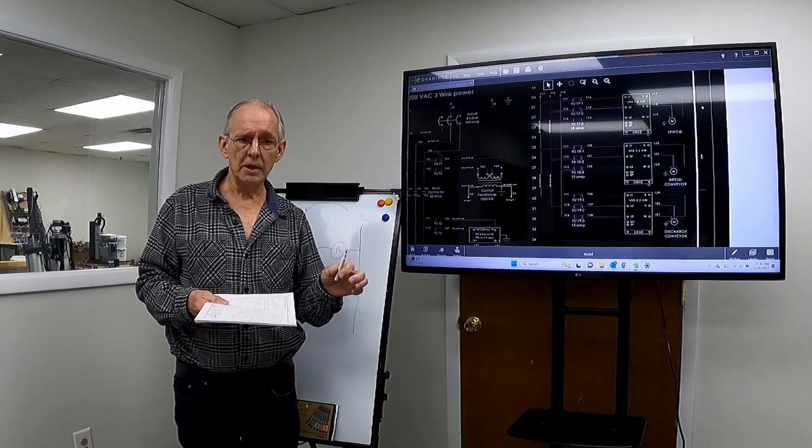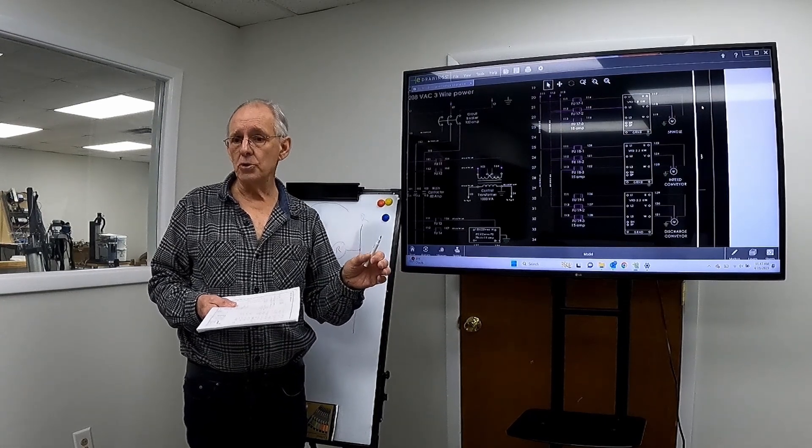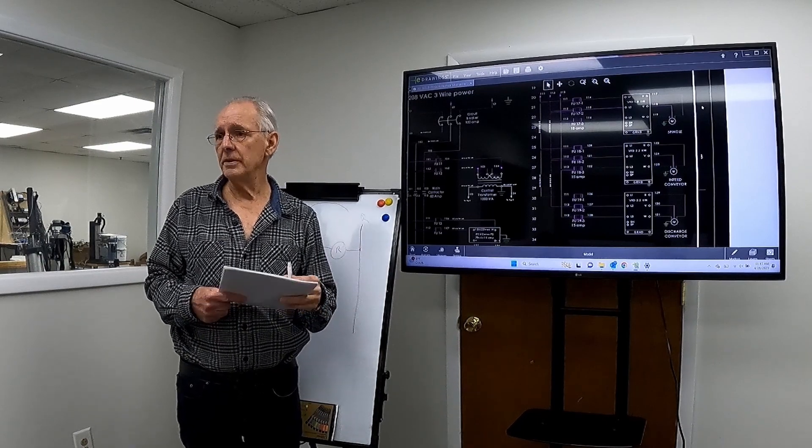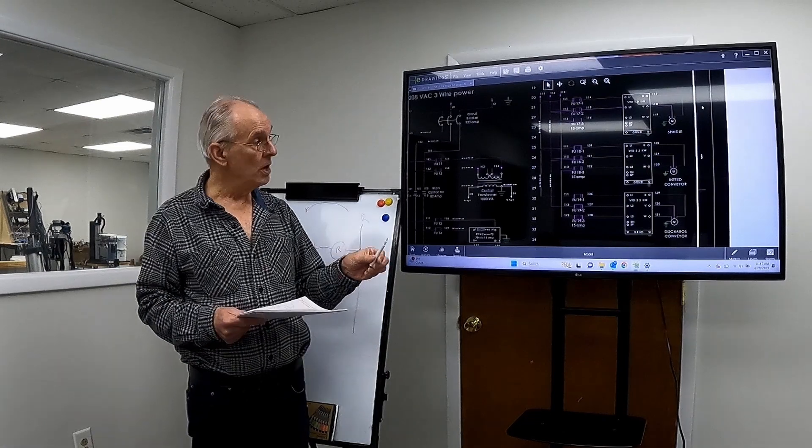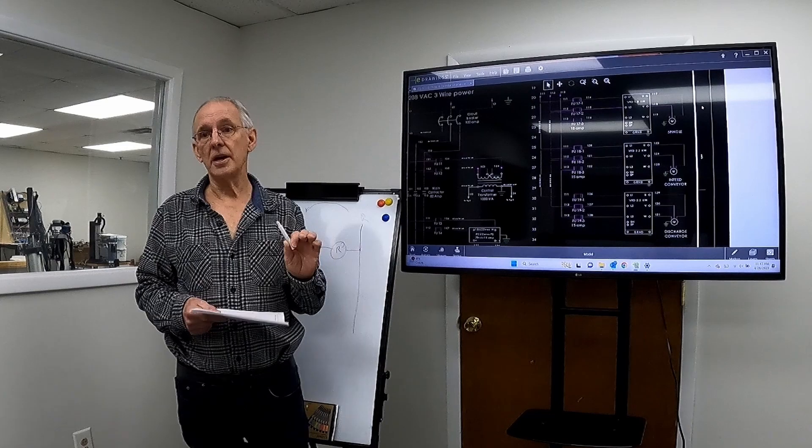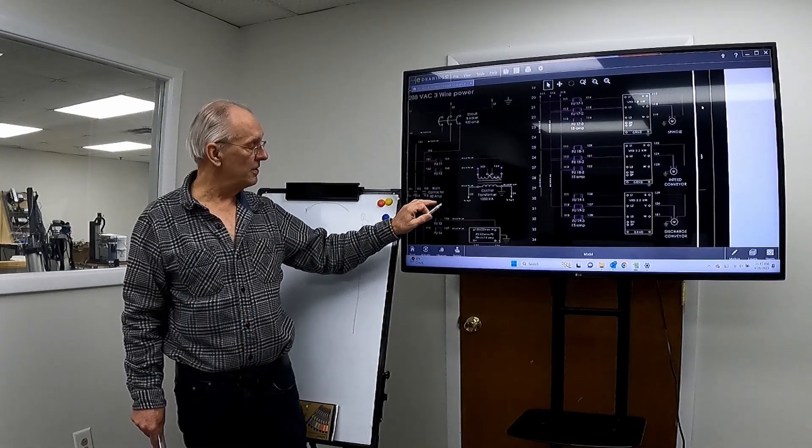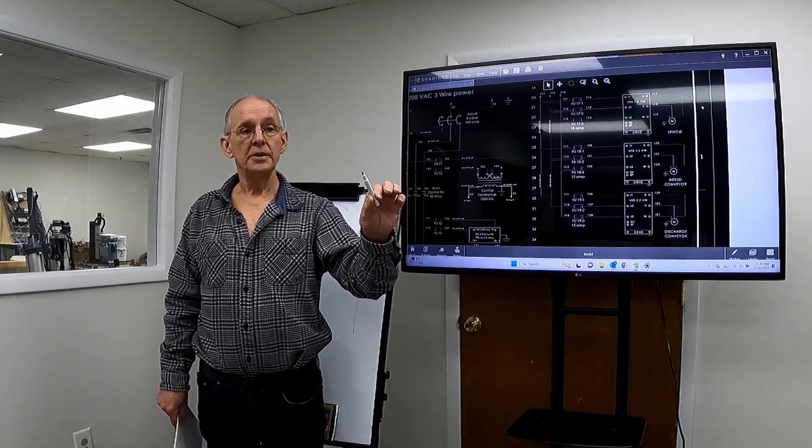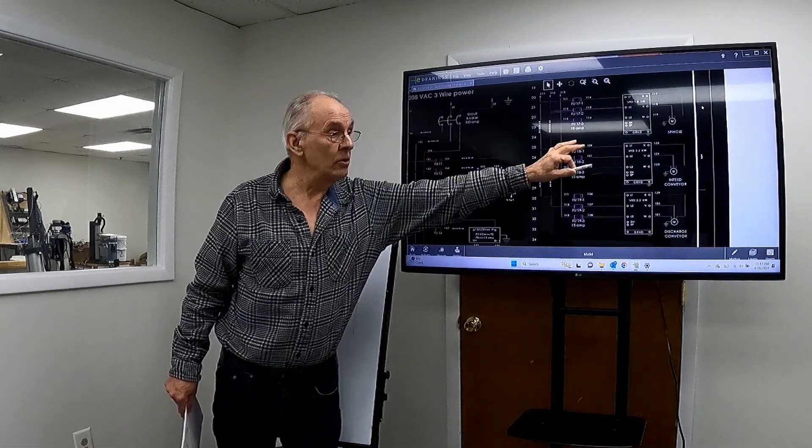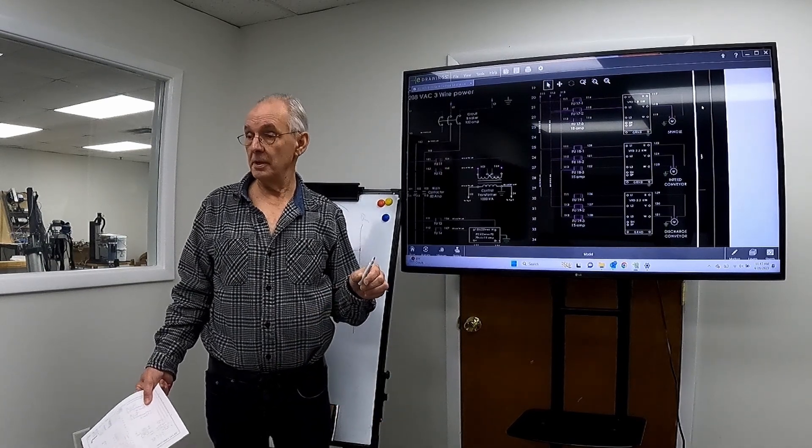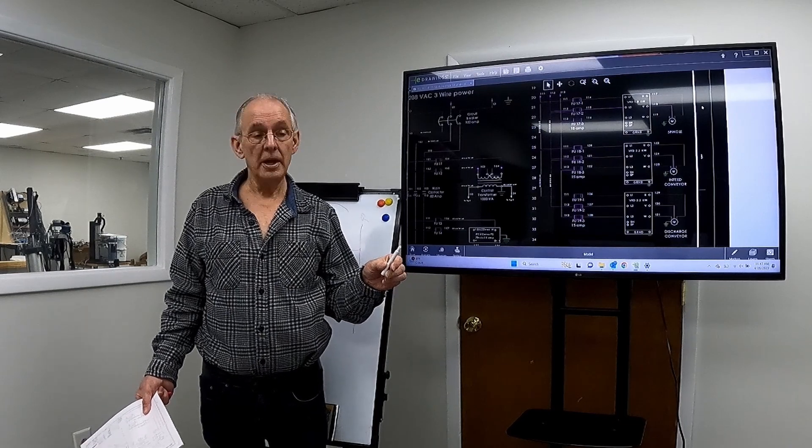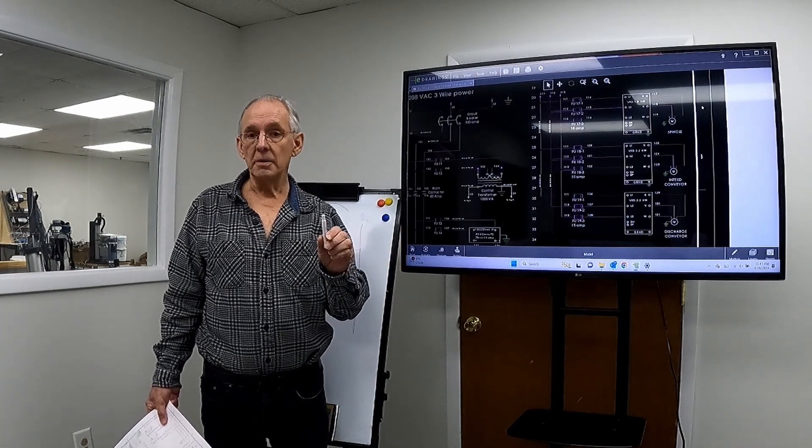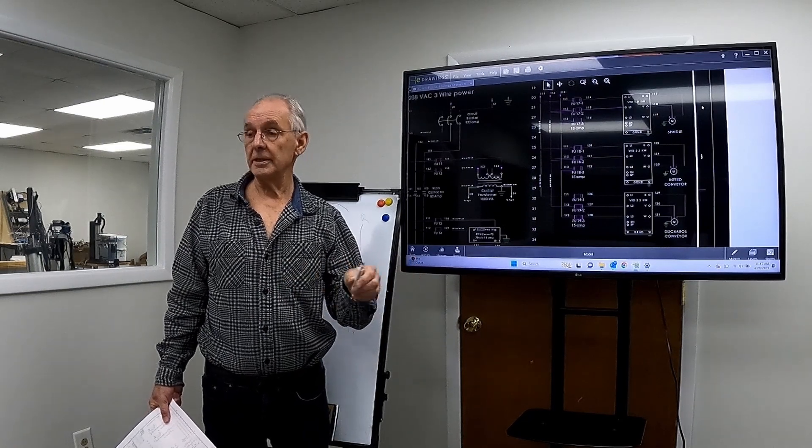So in doing safety, what we do is we try to break as much of the things that can turn on as possible. So we're shutting off the VFDs' power, but what if this contactor failed? Well, in order to keep that from being a problem, we also break the outputs from the PLC that tell them to run. So that's where the safety gets complicated because there's a lot of redundancy involved, and so we break the output power to things like valves and stuff like that.